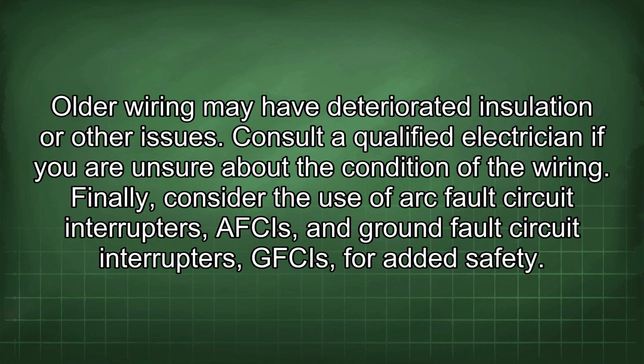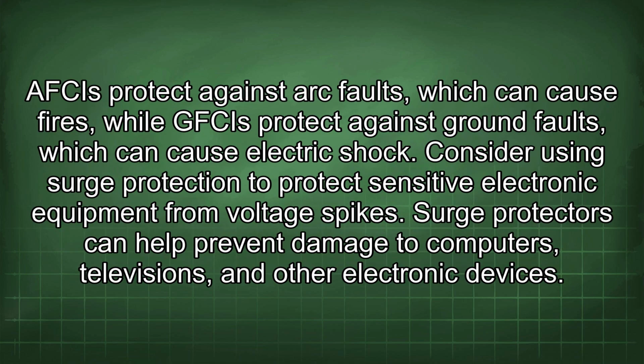Finally, consider the use of arc fault circuit interrupters (AFCIs) and ground fault circuit interrupters (GFCIs) for added safety. AFCIs protect against arc faults, which can cause fires, while GFCIs protect against ground faults, which can cause electric shock. Consider using surge protection to protect sensitive electronic equipment from voltage spikes. Surge protectors can help prevent damage to computers, televisions, and other electronic devices.